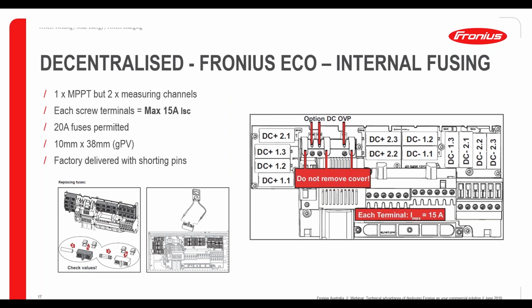The fuse potential is inside the inverter. We send the inverters out with a shorting pin originally in there, meaning that if you did fuse the strings before the inverter, these would stay in there. So it's not a case where the fuses are already installed in the inverter. If you were going to run the strings directly to the inverter, then depending on which inputs you've used, you install fuses in these particular blocks, which are all located in the connection section of the inverter.